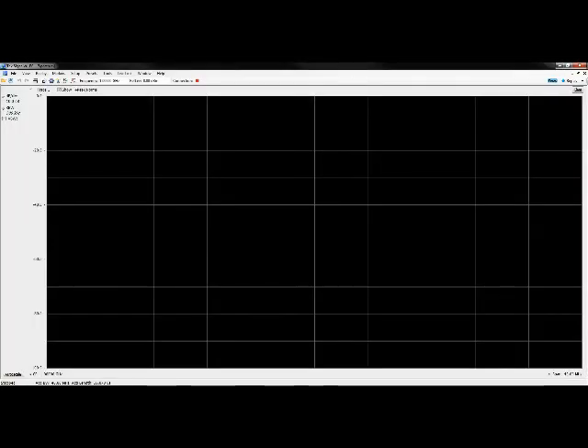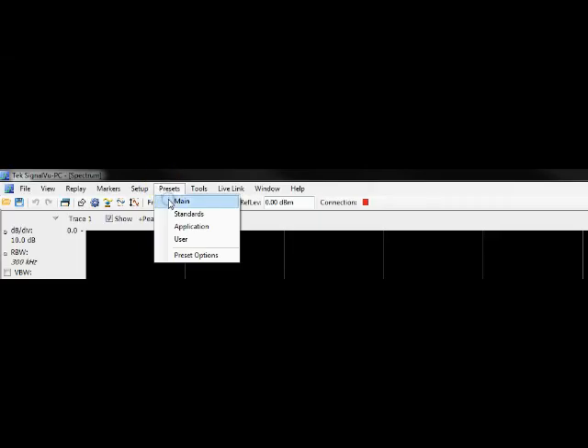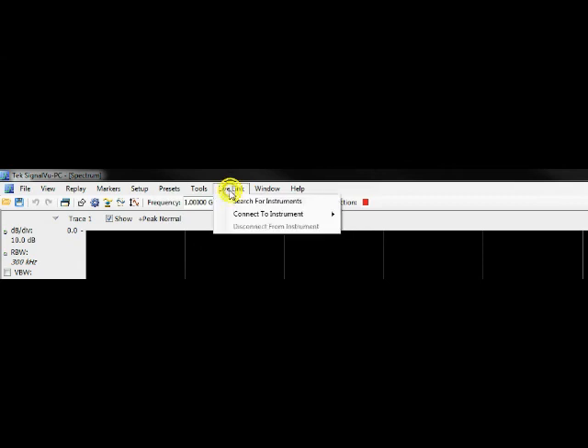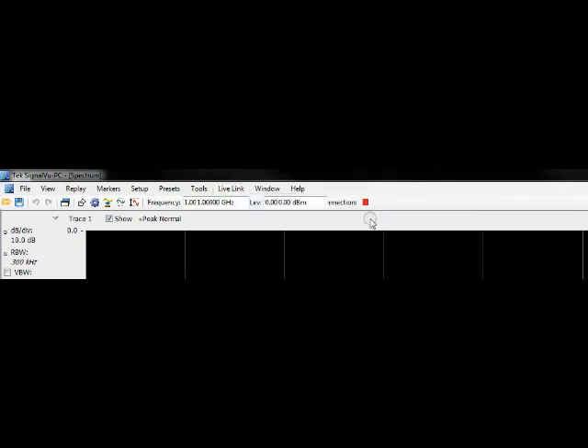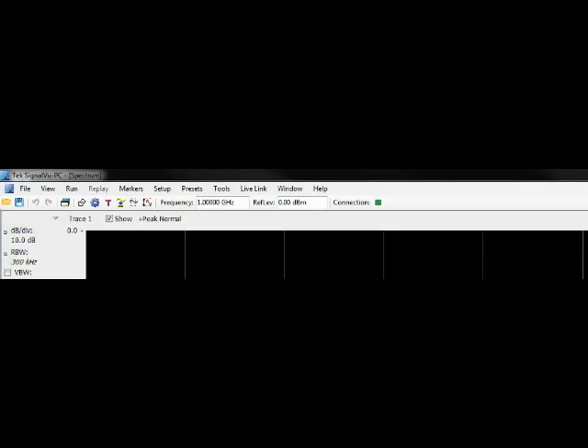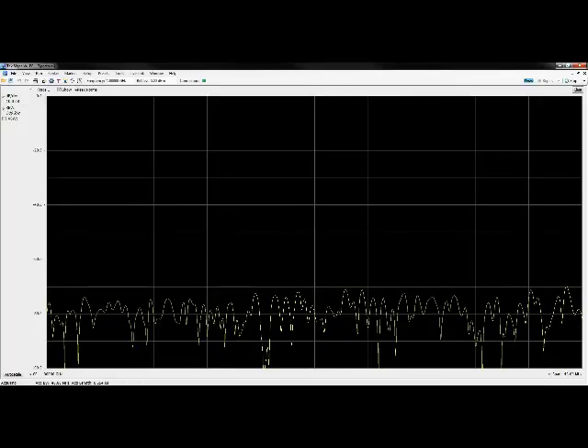Next, open SignalVu-PC. When SignalVu-PC has started, under the Presets menu, select Main. This is much like pressing Default Setup on the scope, but for SignalView. Under the Live Link menu, hover over Connect and click on your instrument. This software is tied to TekVISA, so if you see your instrument in TekVISA, you should see your instrument here. Give it a second to establish connection, and there you have it — all connected.